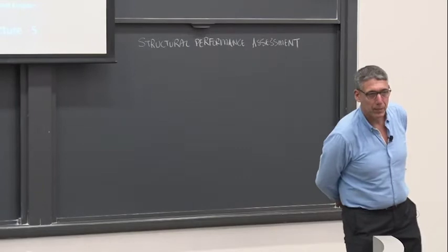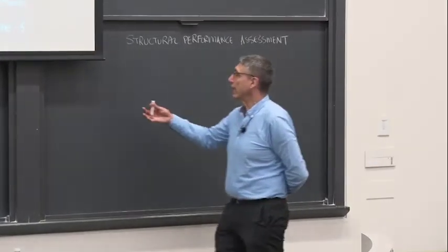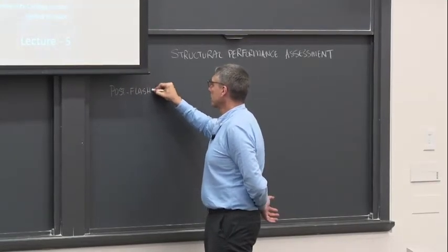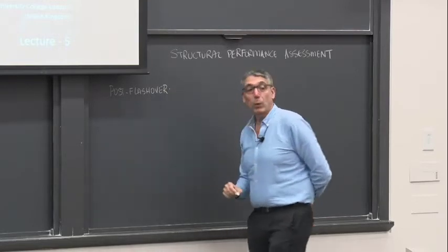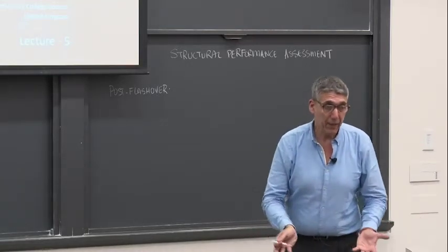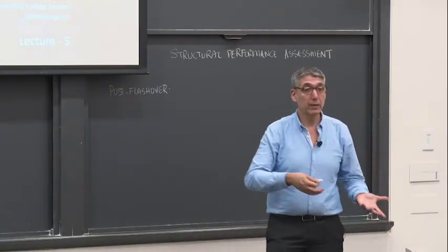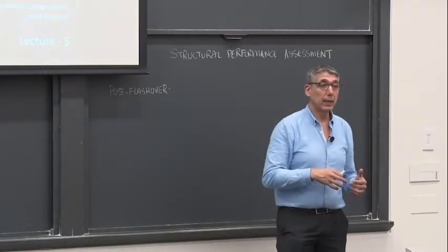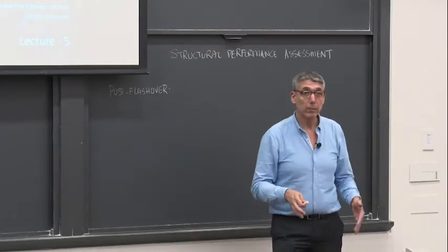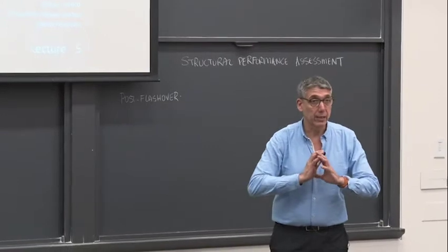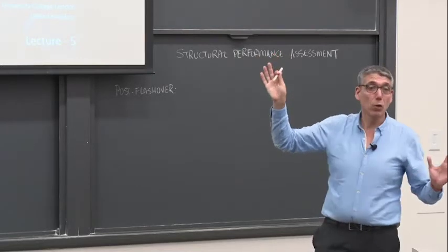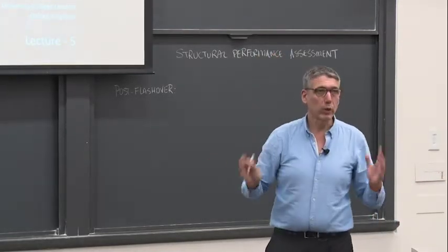Post-flashover? Okay, so clearly we do have that scenario of the post-flashover. We characterized it as an event that involves the entire compartment, with a fairly high temperature, much higher than the growth period. And clearly it's going to last a very long period of time because you have to burn all the fuel. That represents the baseline scenario, so the post-flashover compartment fire is at the core of what we're doing.